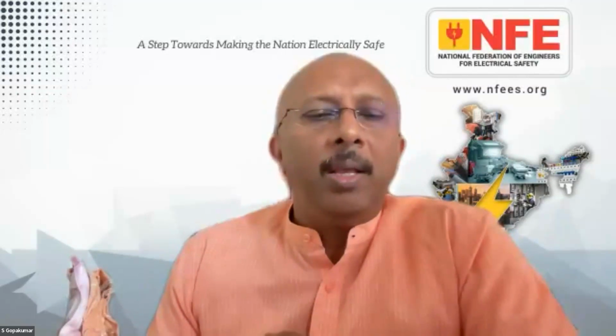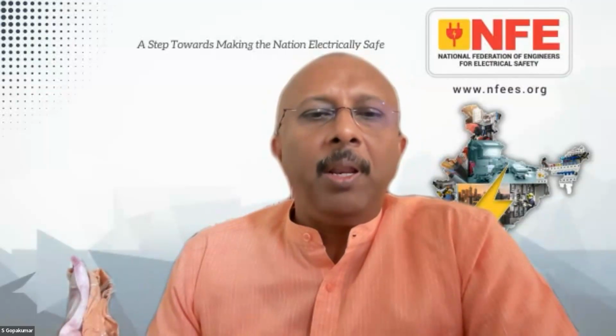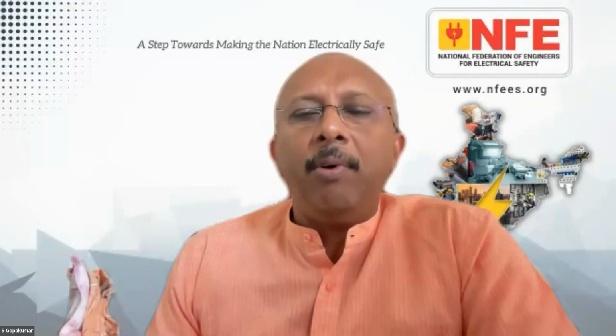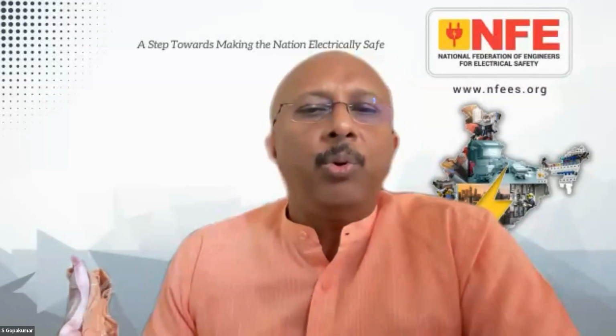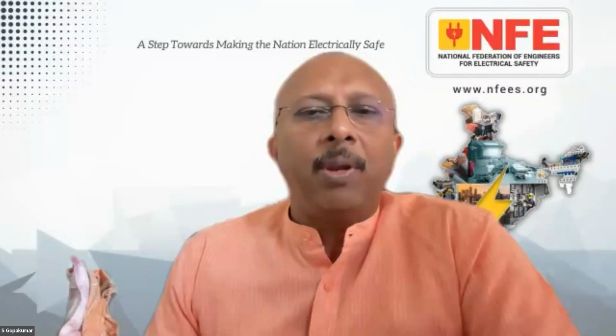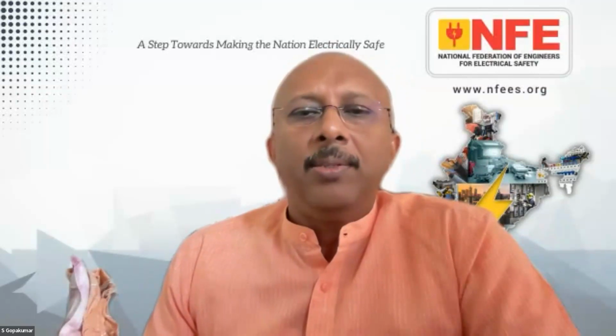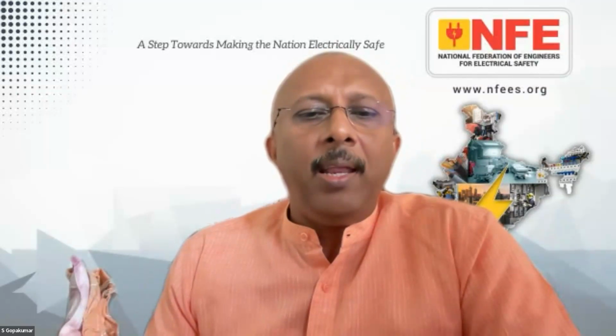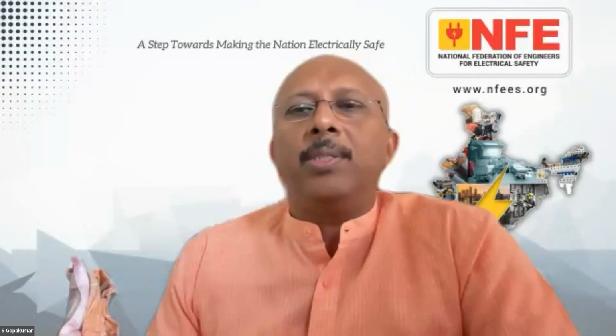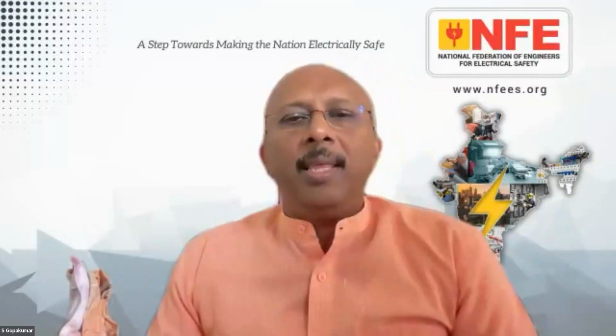So neutral inside the building must be treated like a phase conductor. Never try to connect it to metallic parts in the building. It will create circulating current. Circulating current will create fire, arcing, as well as shock hazard. So it's a violation.